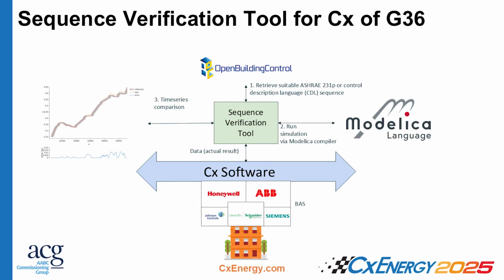We're also looking at integrating some of our in-house tools. Specifically, we have a project called Open Building Control, which is looking at using the ASHRAE 231P standard, which specifies a control description language, right? So in the future, we're going to have these standardized control block sequences, and we can talk about Guideline 36, that basically encodes Guideline 36 in a machine-readable way and could be transferred over to anyone's software, any OEM software, in a way that it's standardized. It's going to be the same on one side of the tool, and when you implement it in the building, you're going to have confidence that it works correctly.